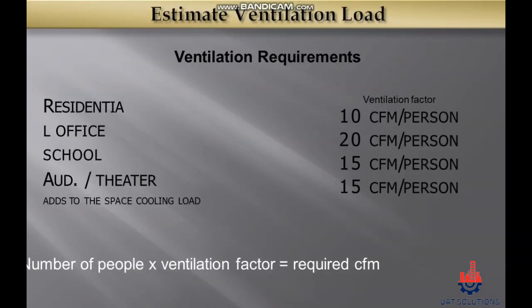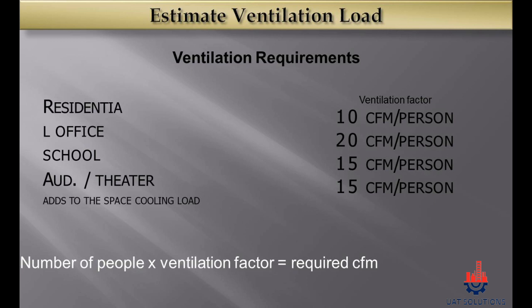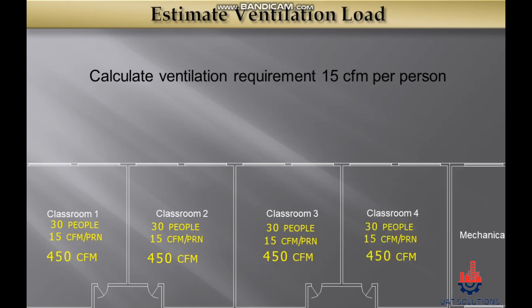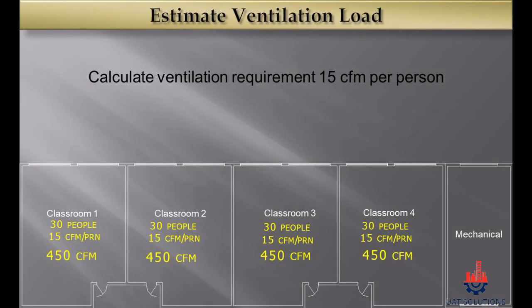The next step is to estimate the ventilation load. We can use the shown ventilation factors to calculate the CFM for ventilation required: 10 CFM per person for residential, 20 CFM per person for office, 15 CFM per person for school, and 15 CFM per person for theater buildings. The formula is: number of people multiplied by the ventilation factor equals required CFM. Assuming 30 people in one classroom and 15 CFM per person, we multiply 30 by 15 to get 450 CFM for ventilation load.